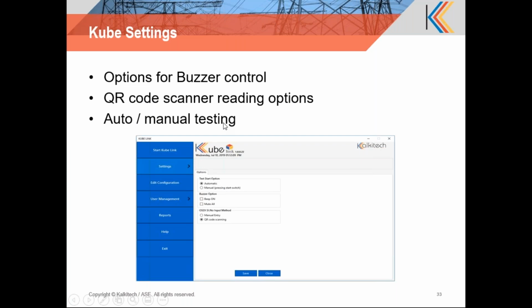Some customers don't opt for manual operation of the buttons. Instead, they want the test to start once the lever is closed, so the test start option is set to automatic. In manual mode, other customers have to manually press the button or make sure they've done all precautions and noted all entries before starting the test. So some customers go for the manual testing mode.